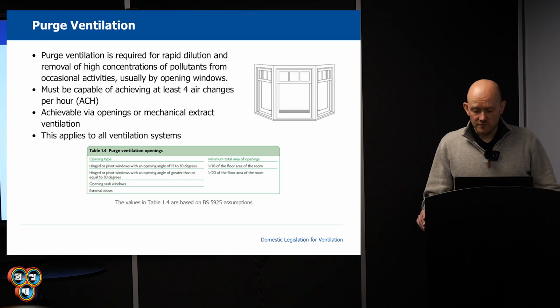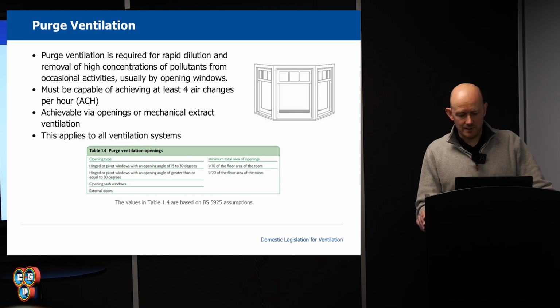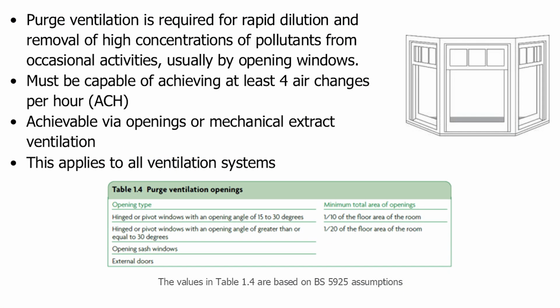A system for purge ventilation is required in each habitable room to remove high concentrations of pollutants from occasional activities, for example, paint smells. Purge ventilation should be capable of extracting a minimum of 4 air changes per hour per room directly to the outside. 4 air changes in a standard bedroom is probably a 6-inch fan. That's the reality of it. So, well, when we get on to Part O, you'll be quite gobsmacked.